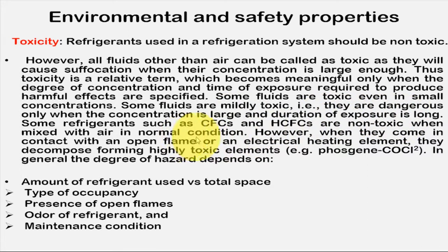Some refrigerants like CFC, HCFC are not toxic when mixed with air in normal condition. However, when they come in contact with an open flame or electrical heating element, they decompose, forming highly toxic elements. So toxicity depends on the amount of refrigerant versus total space, type of occupancy, presence of open flame, odor of refrigerant and maintenance condition.